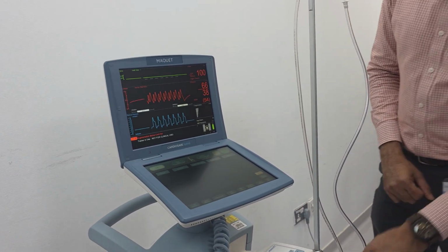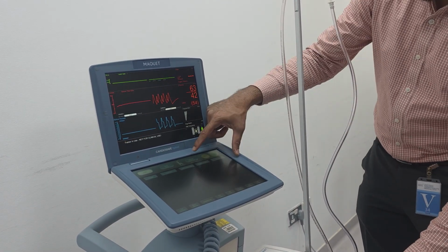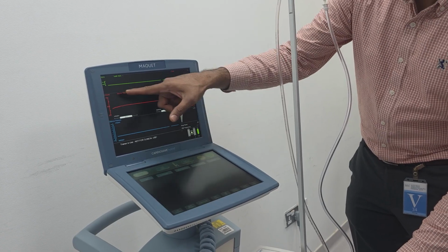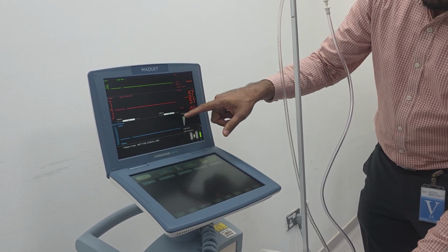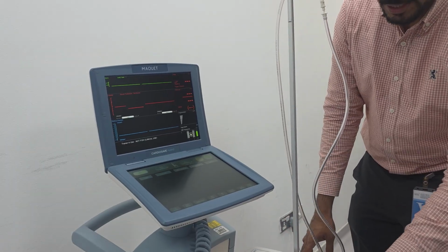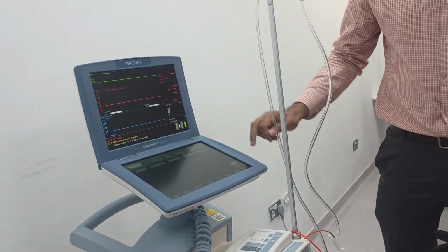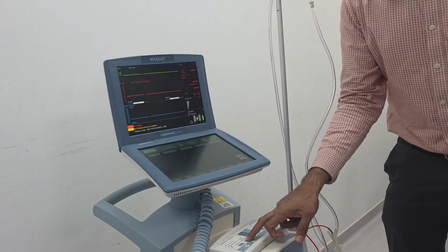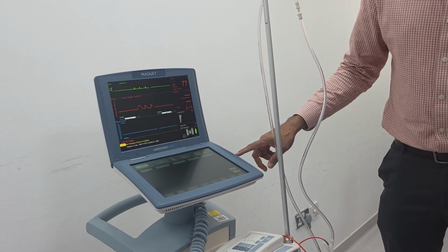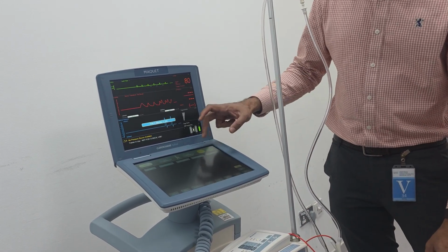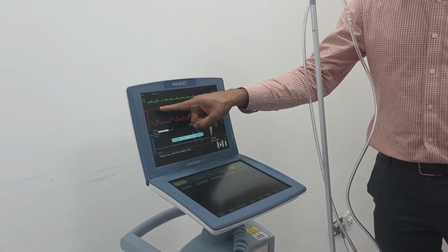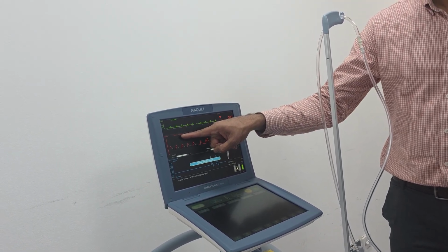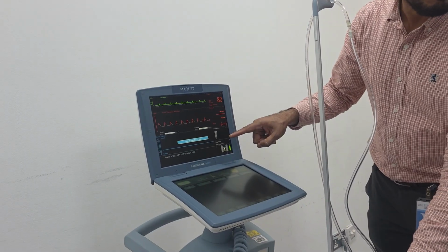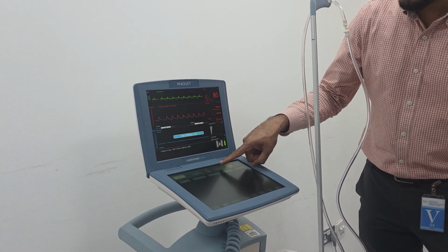Yes. And same, see the difference. It's a calibrate pressure, right? And the source is fiber optic. I'm going to remove my fiber optic, so it will consider ECG pressure, normal balloon. I put standby because it's still in assisted mode. Now it's a normal balloon connection. You can see the source is transducer. You are using a normal balloon with the transducer. And here it becomes 0.